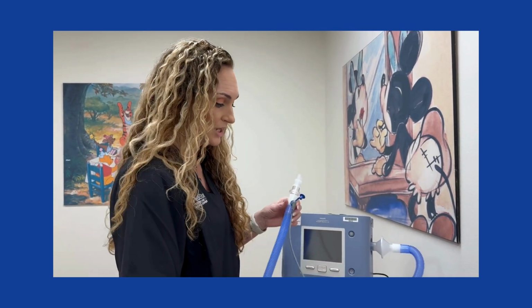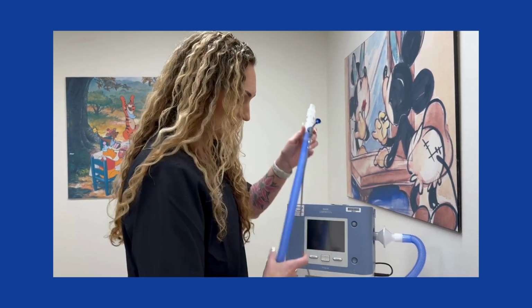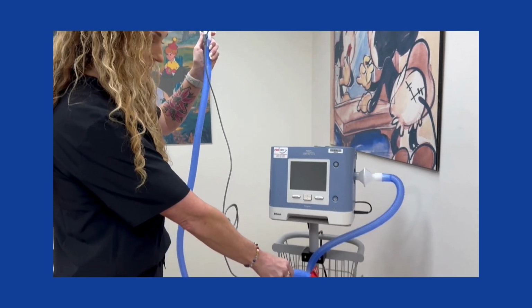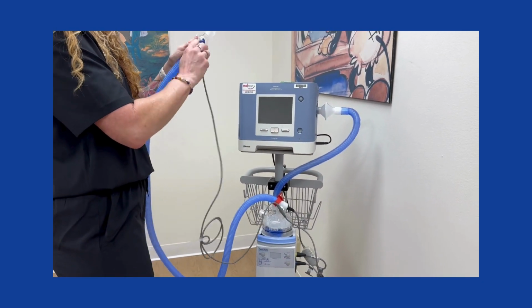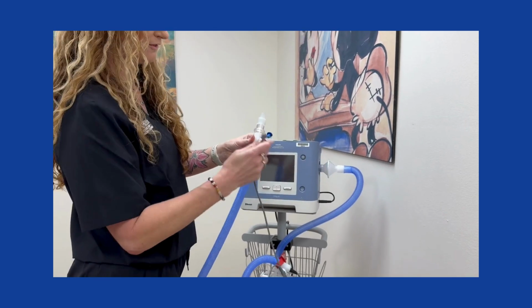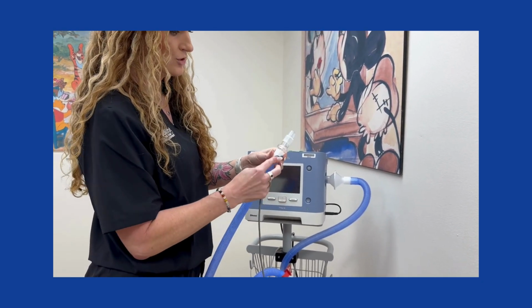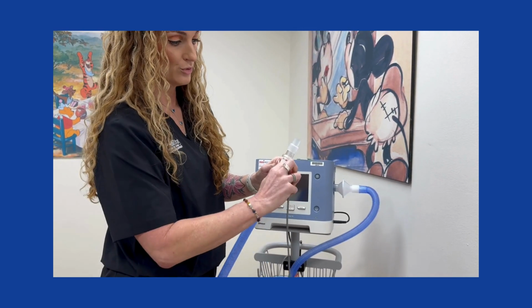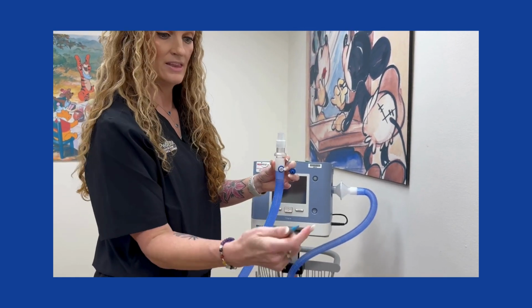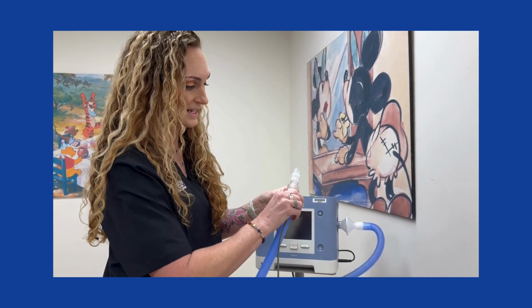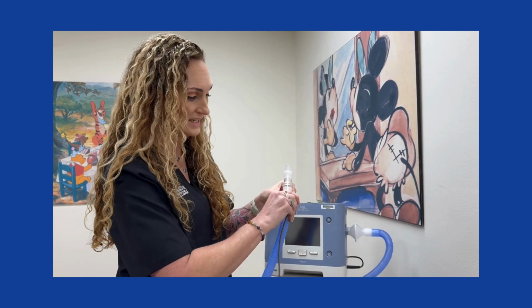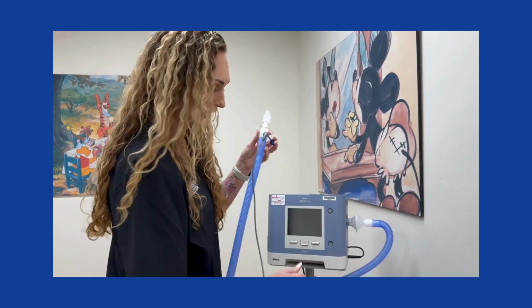So when you're gonna change the circuit, the easiest way to do it is open your new circuit bag and change piece for piece. So what I mean by that is you'll notice you'll have one long piece of tubing. You're gonna wanna take this probe out from the old circuit. The new circuit will have this cap on. You're gonna pull the cap back, and then you're gonna plug in your probe here. And again, match it one for one so it's easy and you don't forget which one goes where.